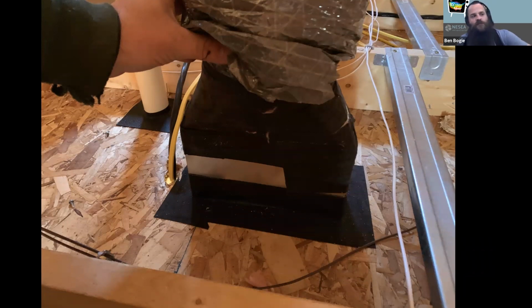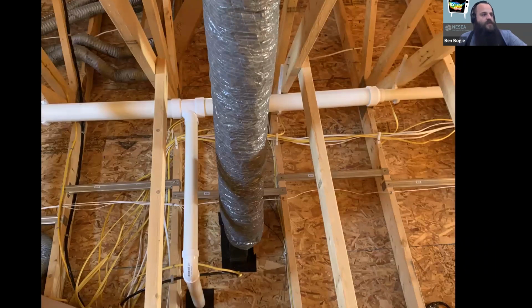The reason it goes to flex is because I want to break the thermal conductivity between the metal duct in the unconditioned space and the metal duct inside the conditioned space, to limit any potential condensation risk. So it goes up into a 3-foot section of flex right here, and then continues on its way up. Next slide.